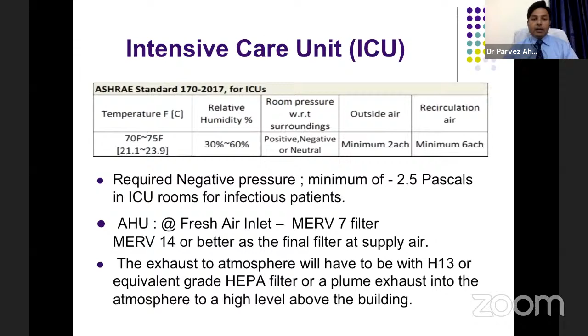Converting general patient rooms or ICU into COVID-19 patient areas. So these are the considerations pertaining to the HVAC system. To convert an existing patient room or ICU into a COVID-19 patient area, it is first necessary to convert the room into a non-recirculatory system, that is, a 100% once-through system. This can be achieved by blocking the return air vents in the patient room.